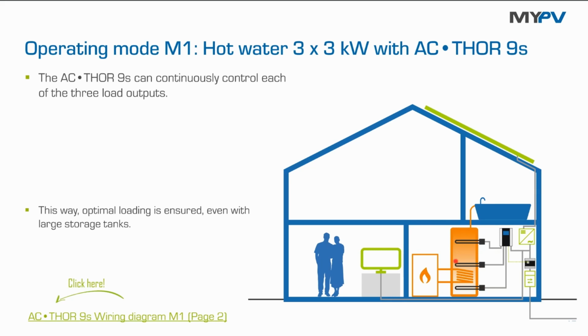And now assume that we have 7 kilowatt peak, 7 kilowatt excessive power available. How does it work then? The heaters on the top and in the middle are switched with nominal power, and the heater at the bottom is controlled linearly. Overall, up to 9 kilowatt are possible maximum, and this happens as long as the thermostats on the heaters are on. When the heater on the top is at target temperature, the thermostat disconnects the load from the AC•THOR 9s, and the AC•THOR continues working with the other remaining immersion heaters.